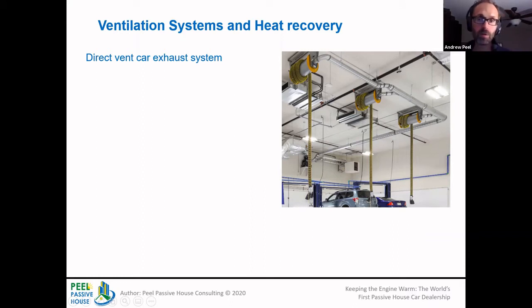In terms of the car exhaust itself, if they're running a car inside, naturally you'd have a buildup of pollutants. So what they do is hook up a long tube to the exhaust pipe, and then through a fan they suck the air from the exhaust pipe outside, and then they have a makeup air unit. We actually looked at connecting the makeup air through a hose to the air intake into the engine at the front.